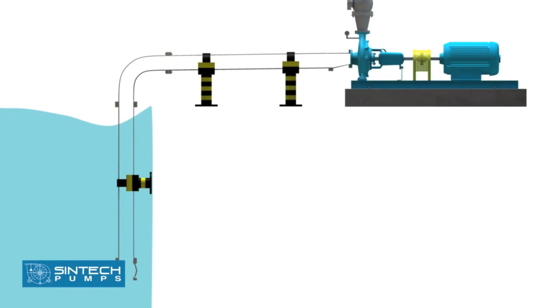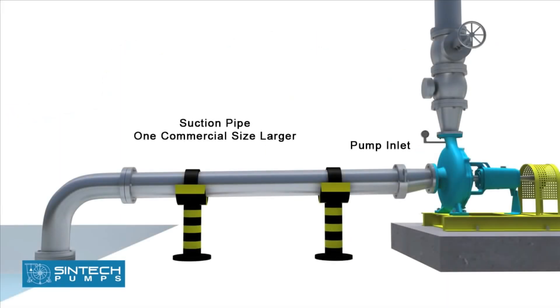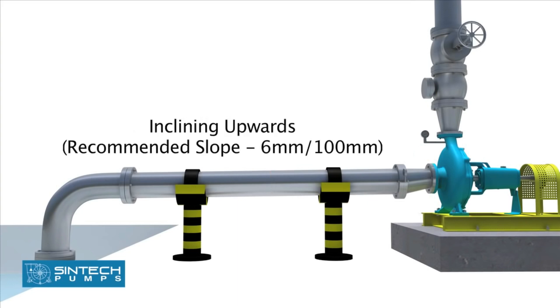The suction pipe should be sized to ensure the liquid velocity of not more than two meters per second. The suction pipe size should be at least one commercial size larger than the opening of the pump inlet. All suction pipes should have a continuous rise to the pump suction inlet. 6mm per 100mm slope is recommended.